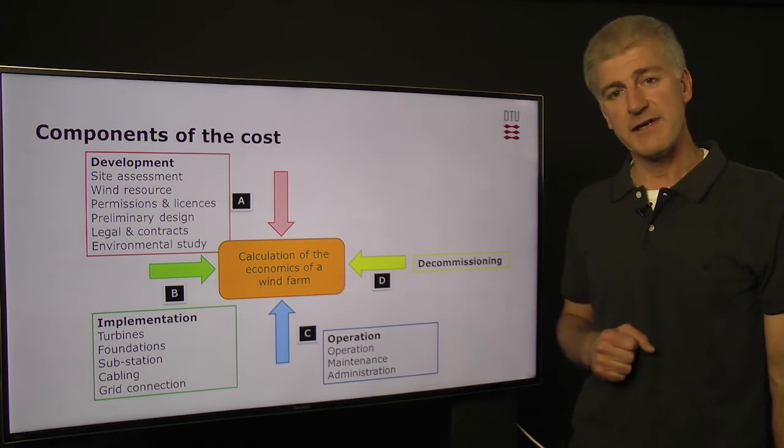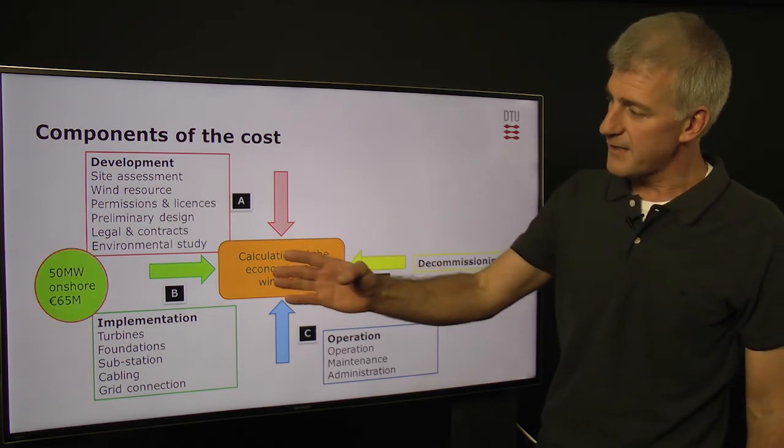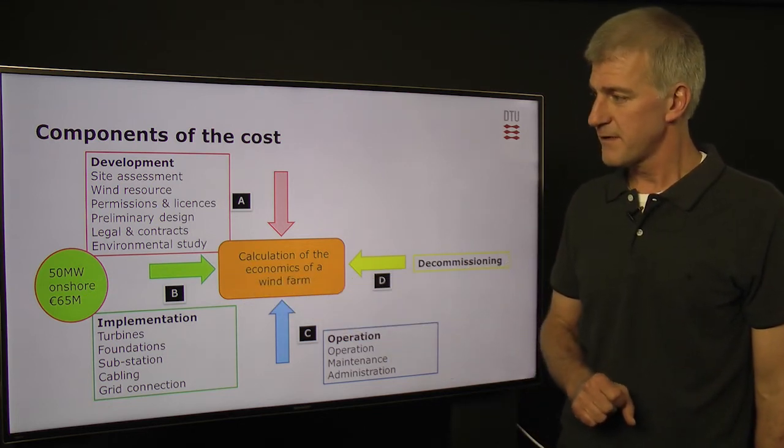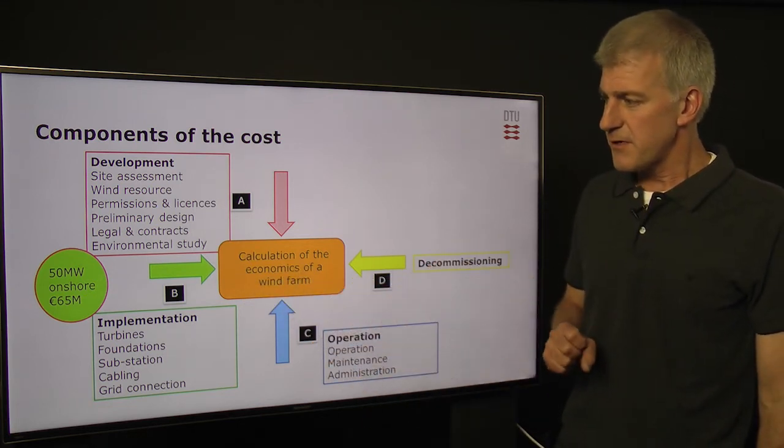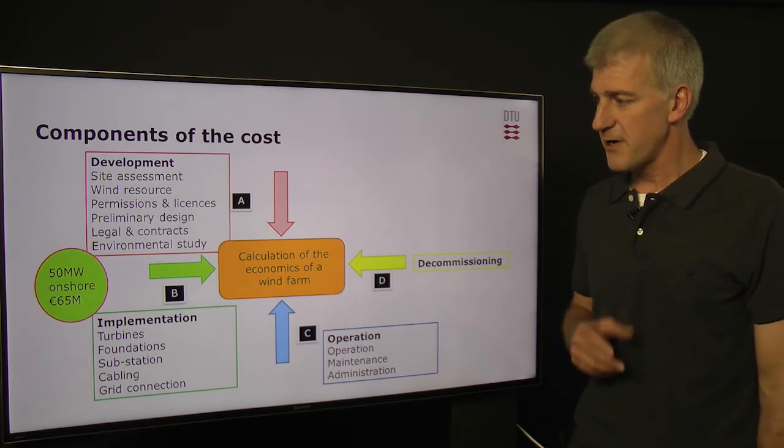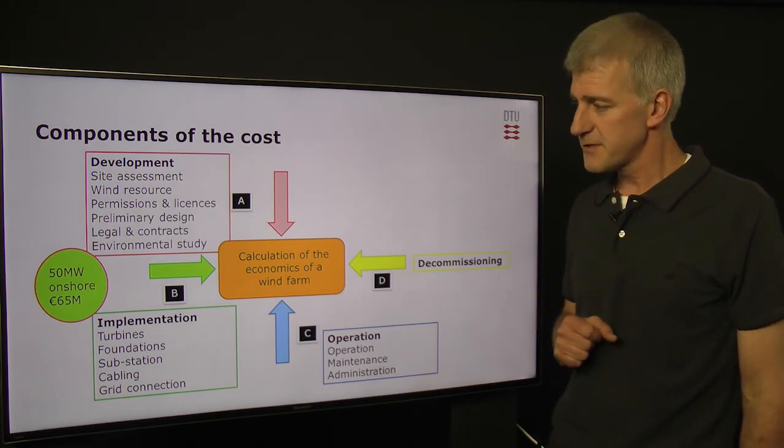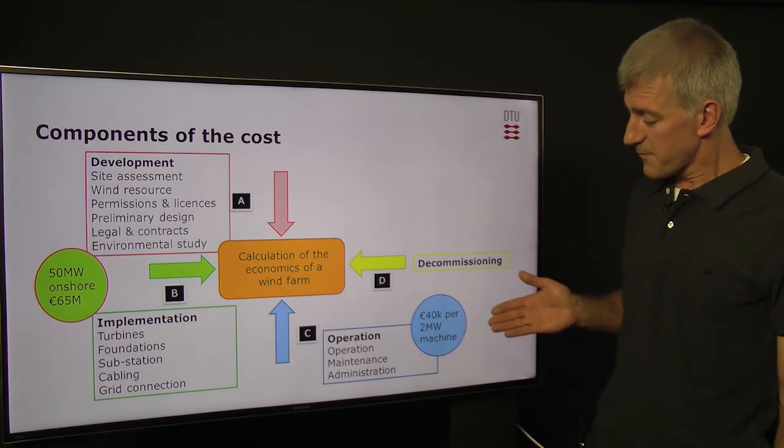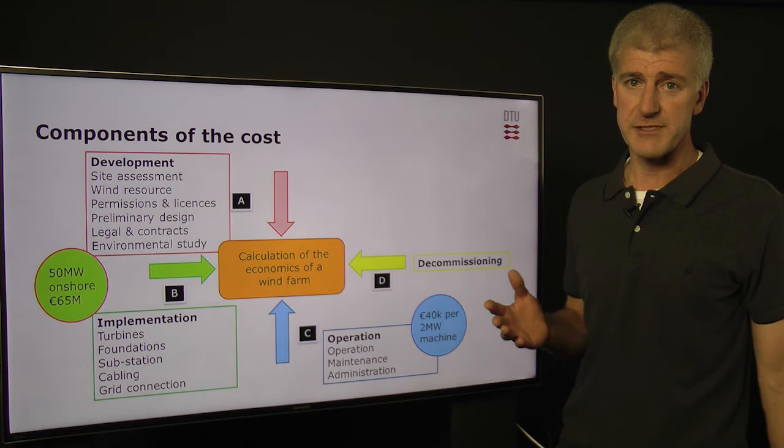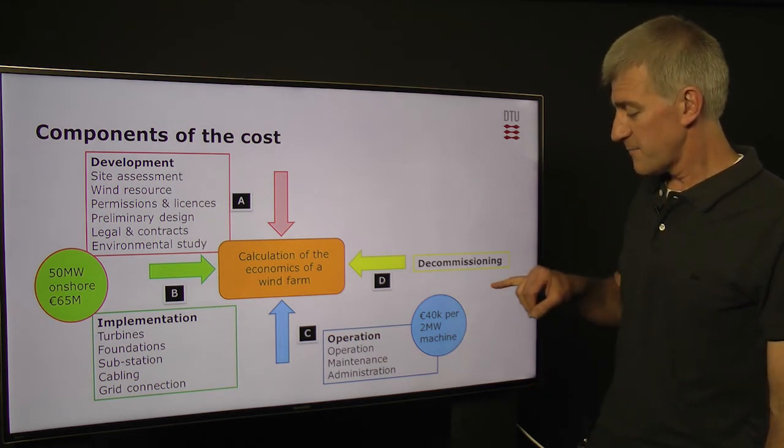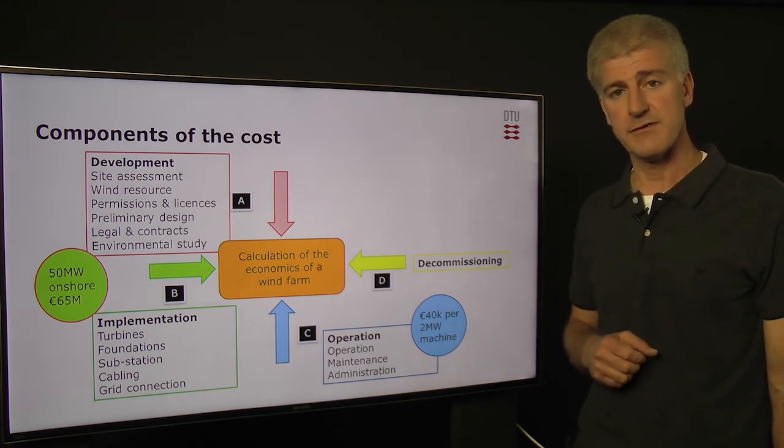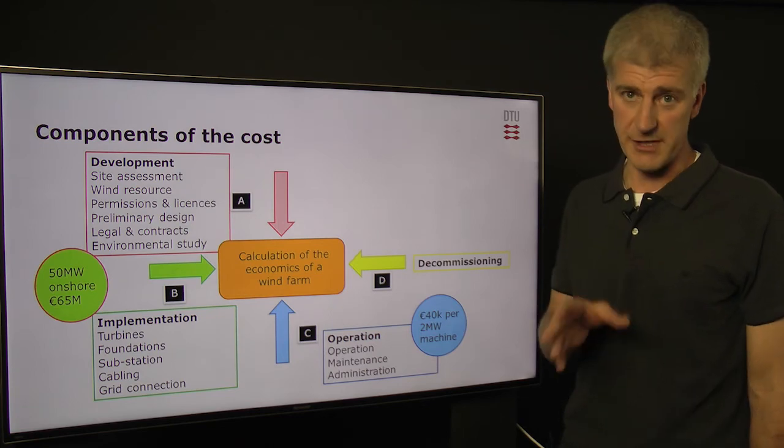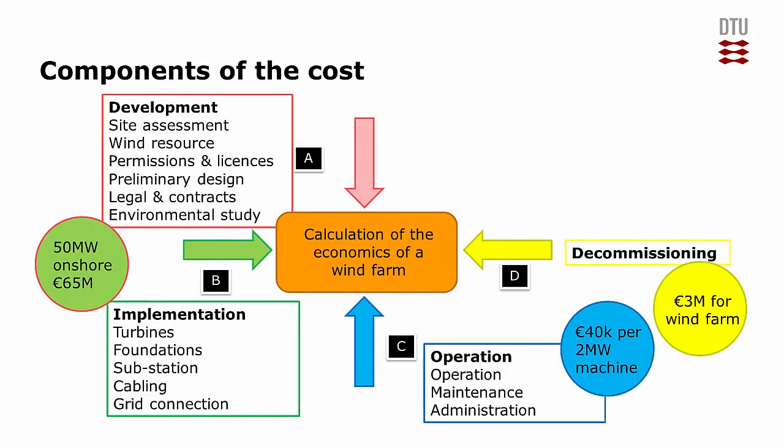How much might these phases cost? Let's just take a look at the development and implementation. For a fifty-megawatt onshore wind farm, we're looking at somewhere around about sixty-five million euros. These are, of course, very approximate figures. For the operation, for a two-megawatt machine, which is a very common size these days, we're looking at about forty thousand euro per machine per year. And finally, for the decommissioning, we might be looking at around about three million euro for the whole wind farm.